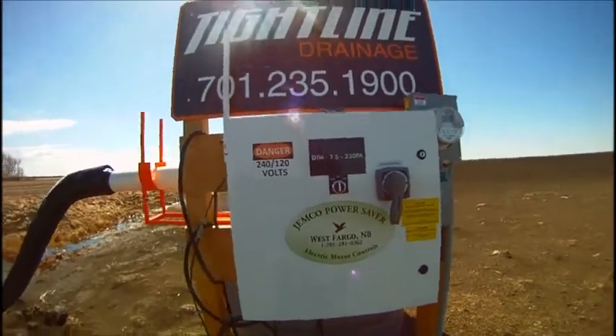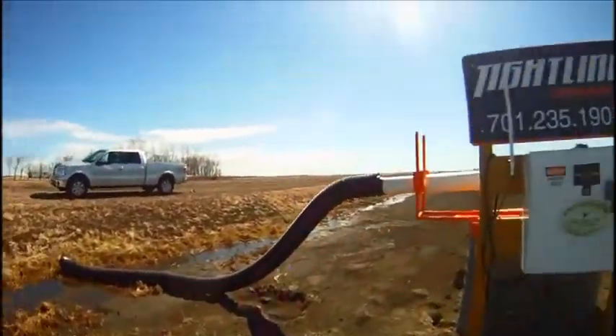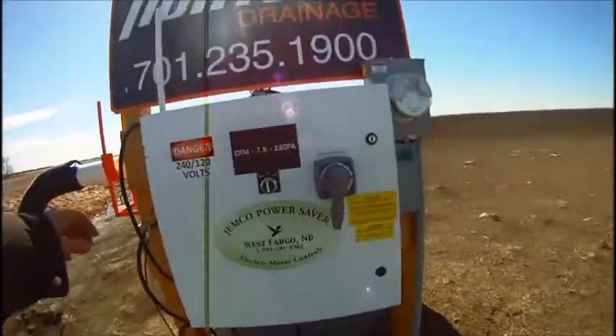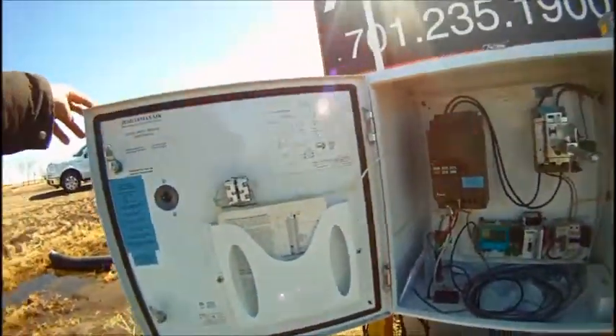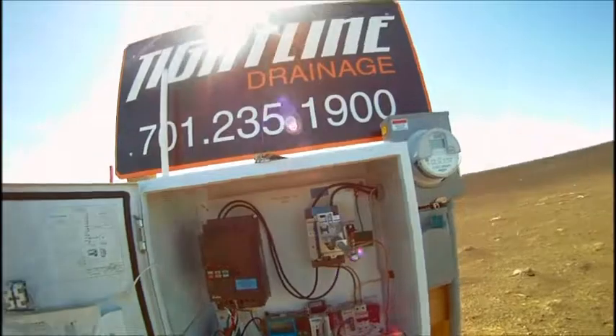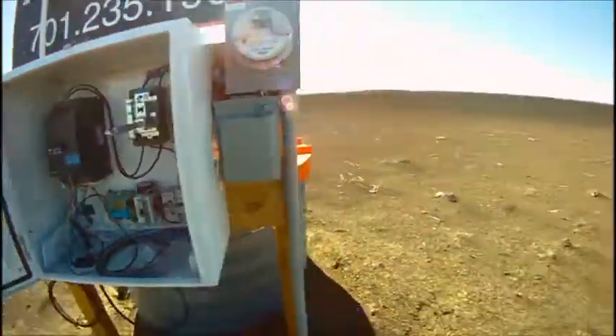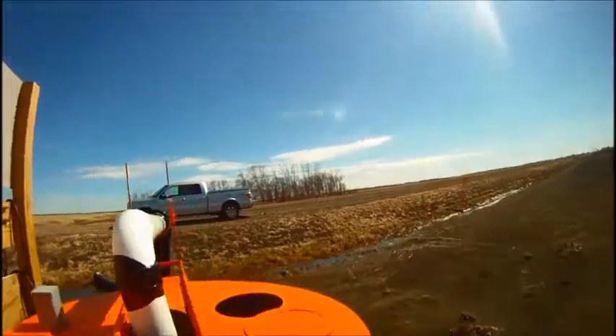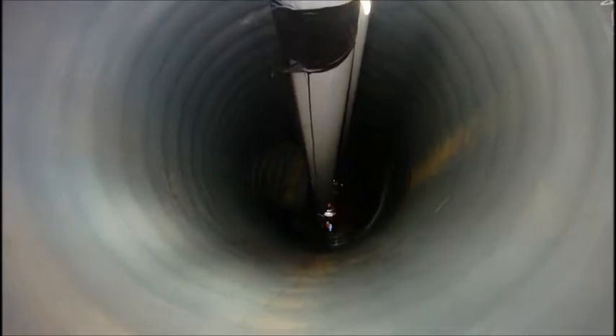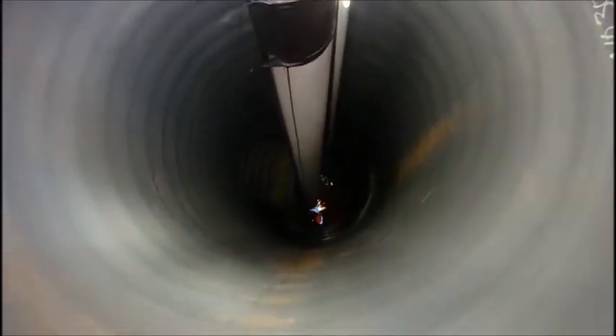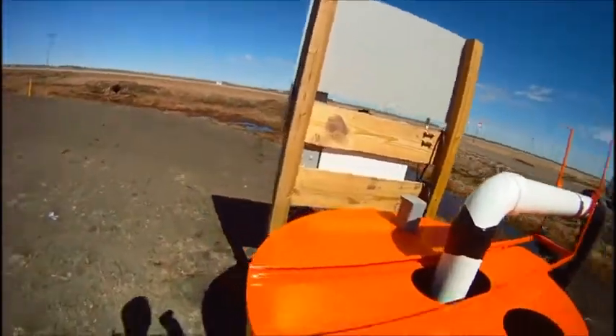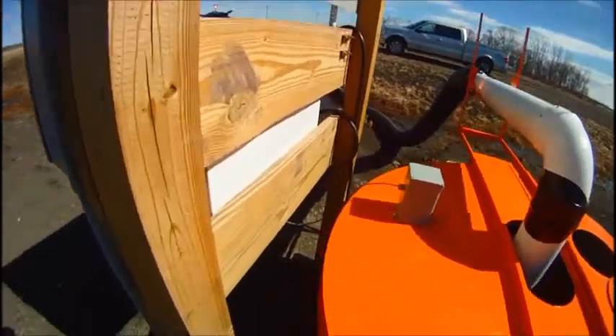So first we'll start with the inspection of the unit and see how the discharge. We want to open up the box, make sure nothing has gotten in there over the winter. Want to take a look at your reservoir. Look into the lift station. This one looks like it's just to the top of the pump. Everything looks good. Doesn't look like anything's gotten chewed or disconnected.